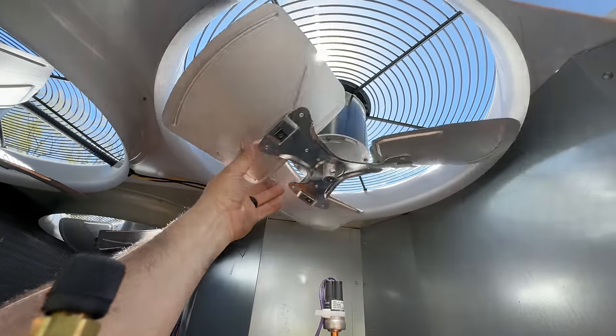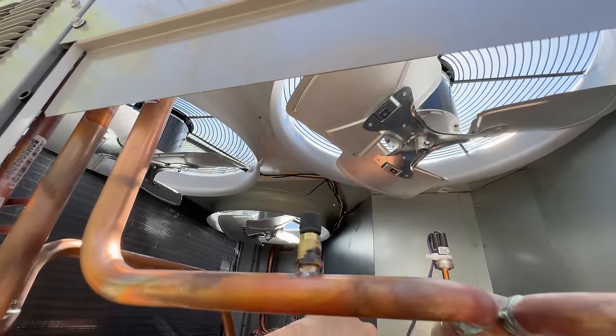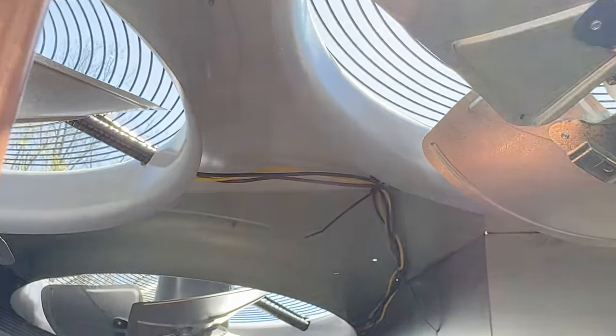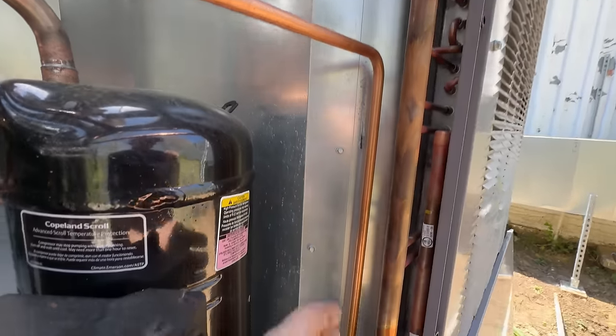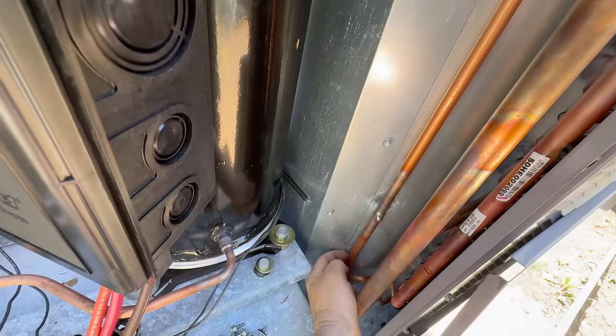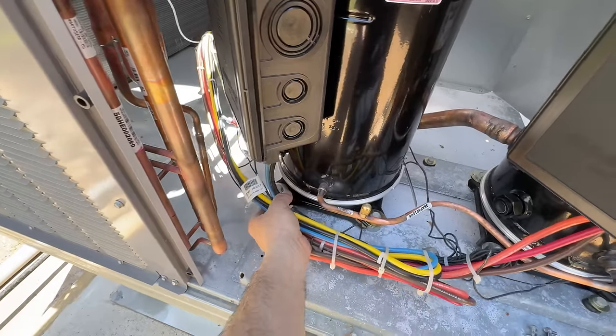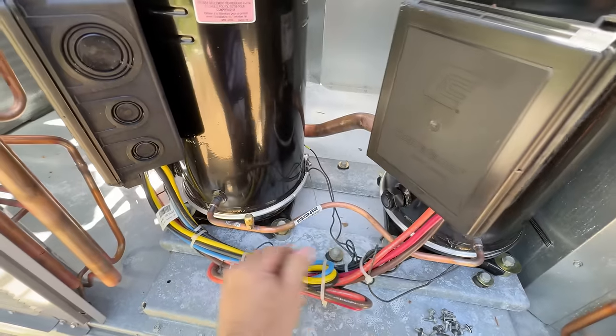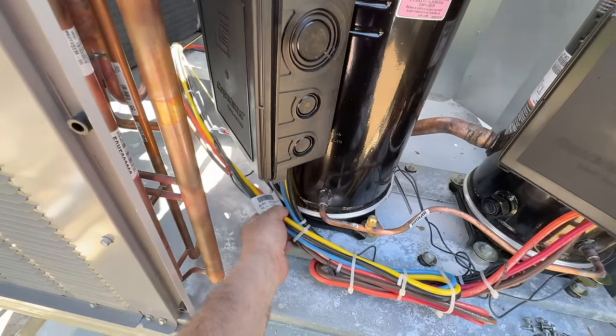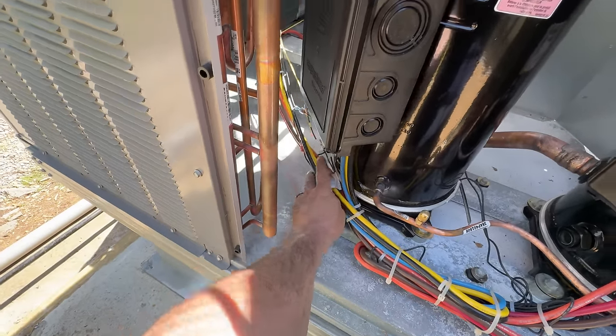You've got to watch for these so they don't rub into anything. Blades are tight, wires look good, nothing dangling. These are the things you've got to look at when you're trying to start it up. This wire is just right up against that heater — I mean it's some thick insulation, but we could wire tie that so it doesn't vibrate. I suppose we could wire tie it around the foot to there and that would hold it.